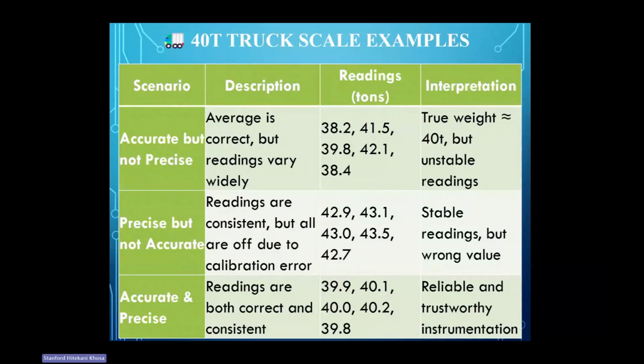Now we look at the second scenario, being precise but not accurate. Here a truck was loaded 42.9, 43.1, 43.0, 43.5, and 42.7. But on the scoreboard, it was reading about 40. When we took it to the weighbridge, this is what we found. When we analyze, we realize that these values are very stable, and you may mistake them for the right data that you need. But when you look at the actual reality, the values do not correspond with what the truck registered on the scoreboard.